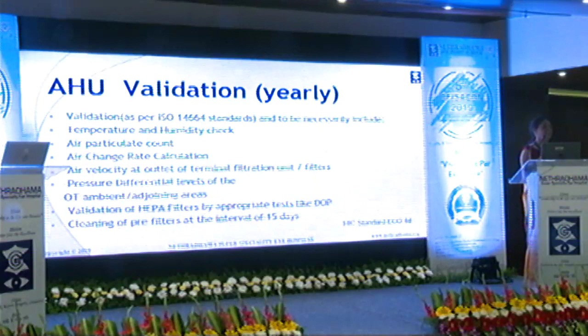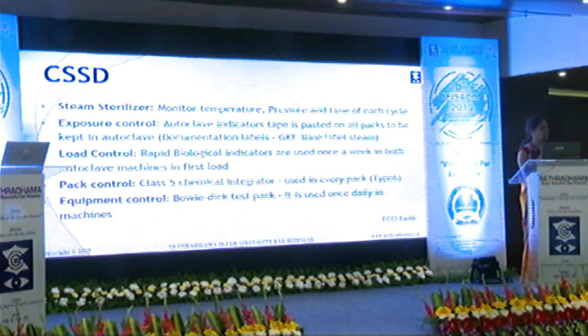CSSD is again the most important part of an operation theatre. Physical parameters for monitoring include the autoclave steam sterilizer's temperature, pressure, and time. Exposure control uses autoclave indicator tapes, and load control uses biological indicators, which should be used at least once a week.